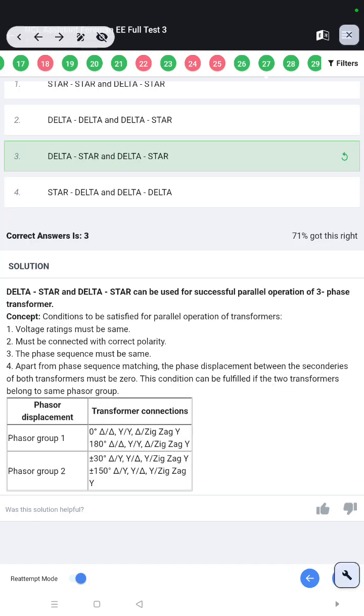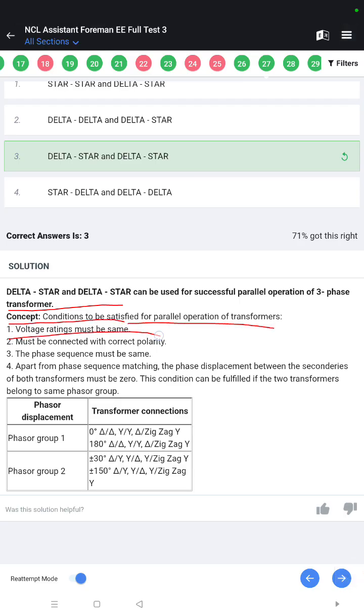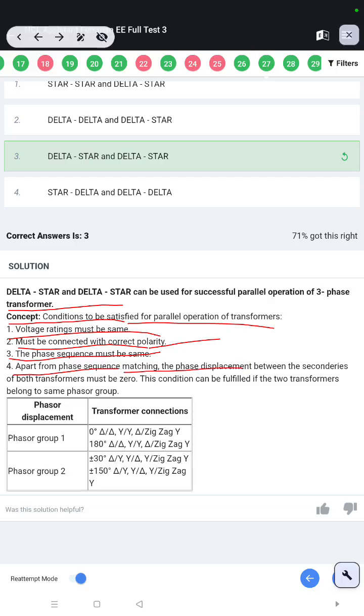Transformer concept: conditions to be satisfied for parallel operation of transformers. First, the voltage rating must be the same. Second, they must be connected with correct polarity. Third, the phase sequence must be the same. Fourth, apart from phase sequence matching, the phase displacement between the secondaries of both transformers must be zero. This condition can be fulfilled if the two transformers belong to the same phasor group. Phasor group 1.